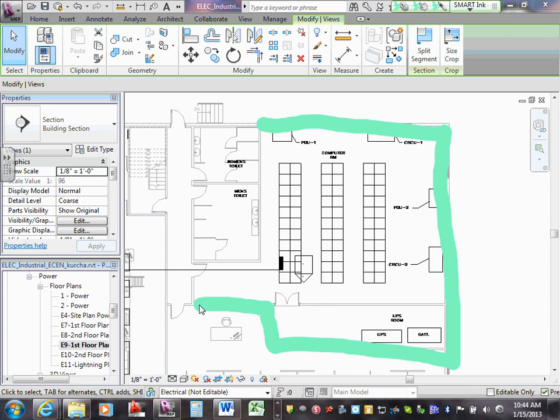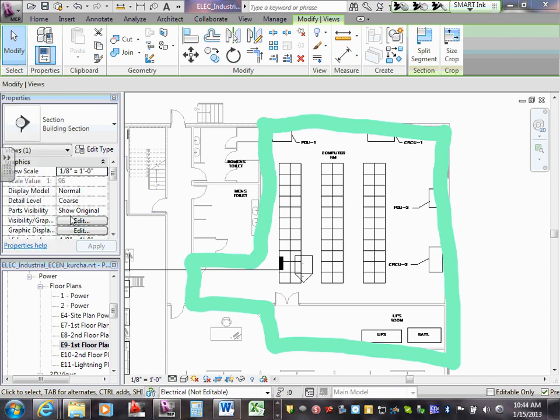Let's see here. This raised floor? Yep. Drop ceiling? Yep. Okay. On a raised floor, the code requires that depending on the number of air exchanges is how you're going to reduce your smoke detector spacing. Starting at 30 feet on center, 900 square feet, and depending on the amount of air exchanges, it can go all the way down to 9 feet on center.